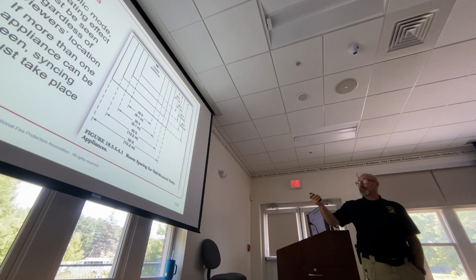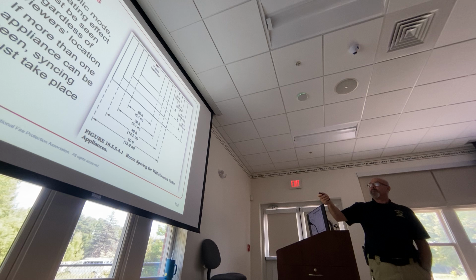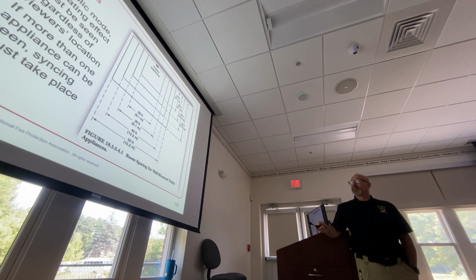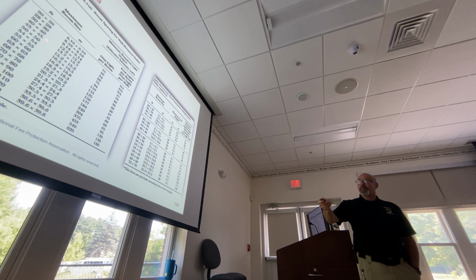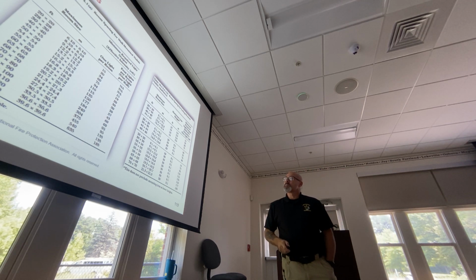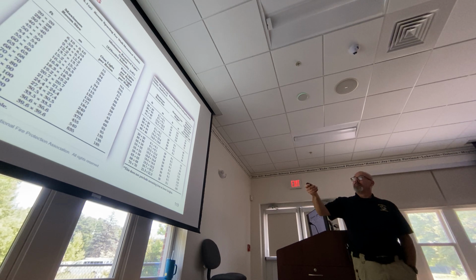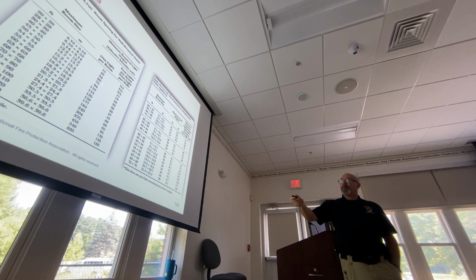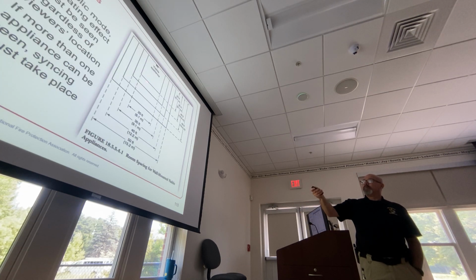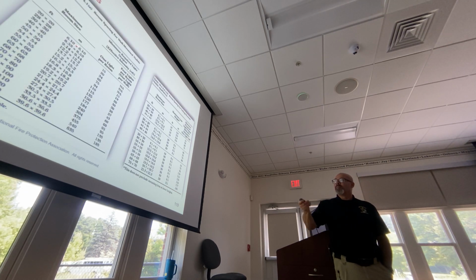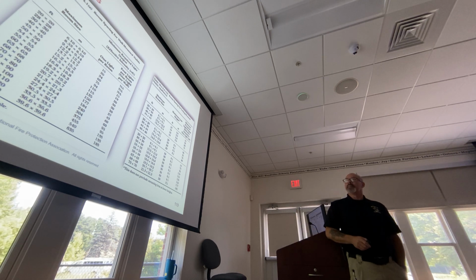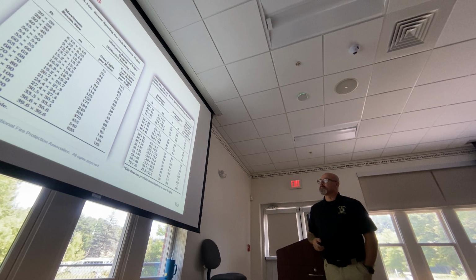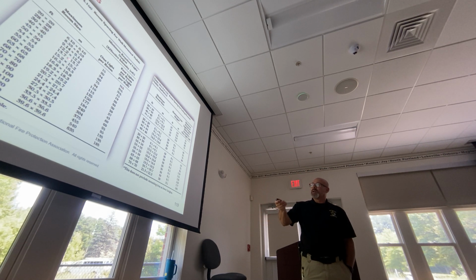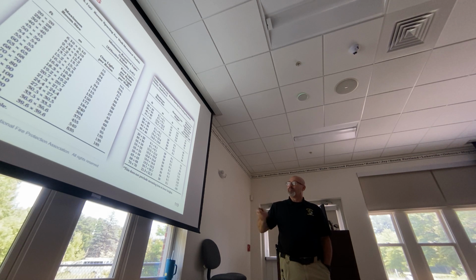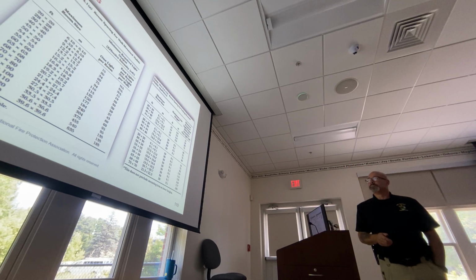Going back to this, room spacing for wall-mounted visual appliances, all this is showing you the 20 by 20 box, 30 by 30, 40 by 40, 50 by 50. You go to this table, 20 by 20, 30 by 30, 40 by 40, 50 by 50, and it continues to go. So if I have a 20 by 20 room, I have to have one light per room, and it has to be at least 15 candela. So if I'm in this room here, I have to have at least one light in that room that is 15 candela, CD, okay? I don't have to have 4 lights, and not applicable. Once I get up to a 40 by 40 room, if I have one light, it's gonna be 60 candela, or I have to have 4 of them that are 15 candelas each. Does that make sense?